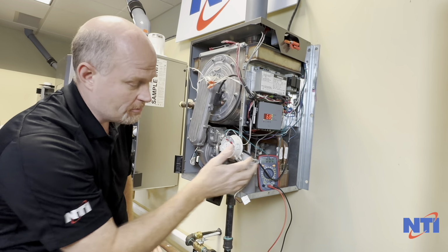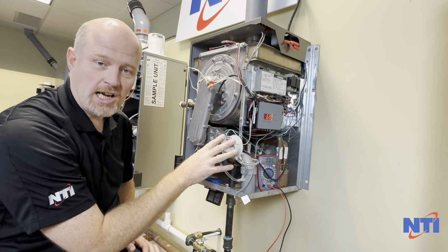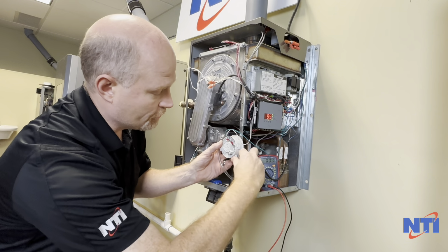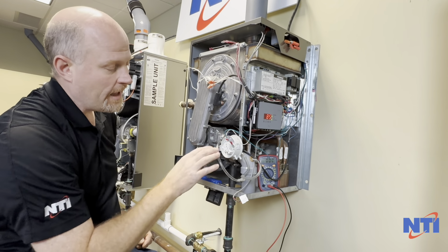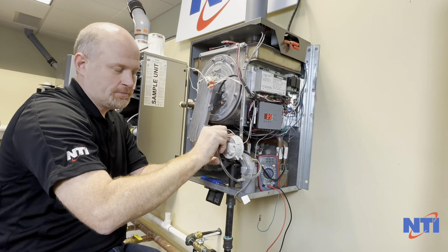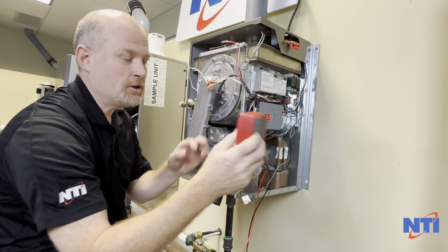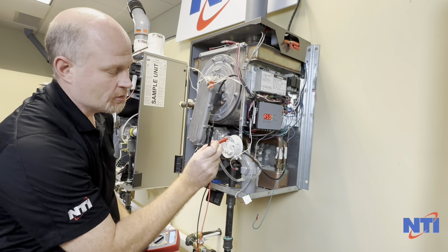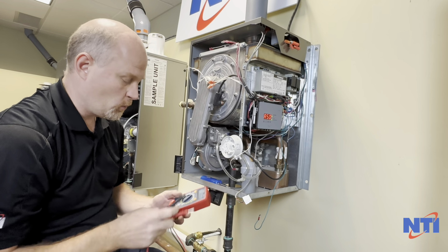Failing the tubing being blocked or the fan failing, at that point you may have an air switch that's stuck in the closed position, and the way to test that is to either turn your boiler off or disconnect both tubes. So we're going to remove both tubes here. We're going to remove the wires, and if I test my air switch when it's just sitting here idle, it should be an open circuit between wire contacts numbers 1 and 3. So number 1 is the middle contact, and in this case number 3 is the contact closest to these ports.